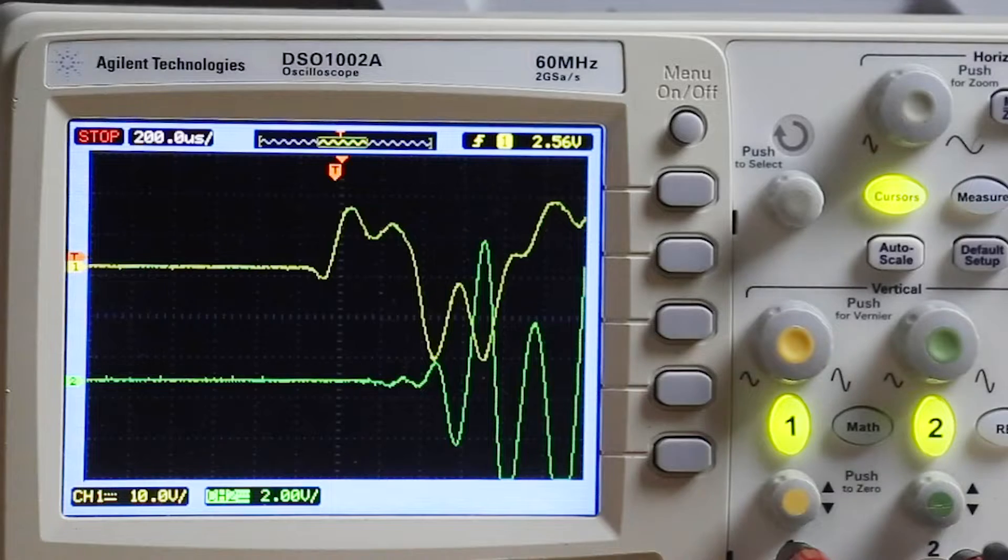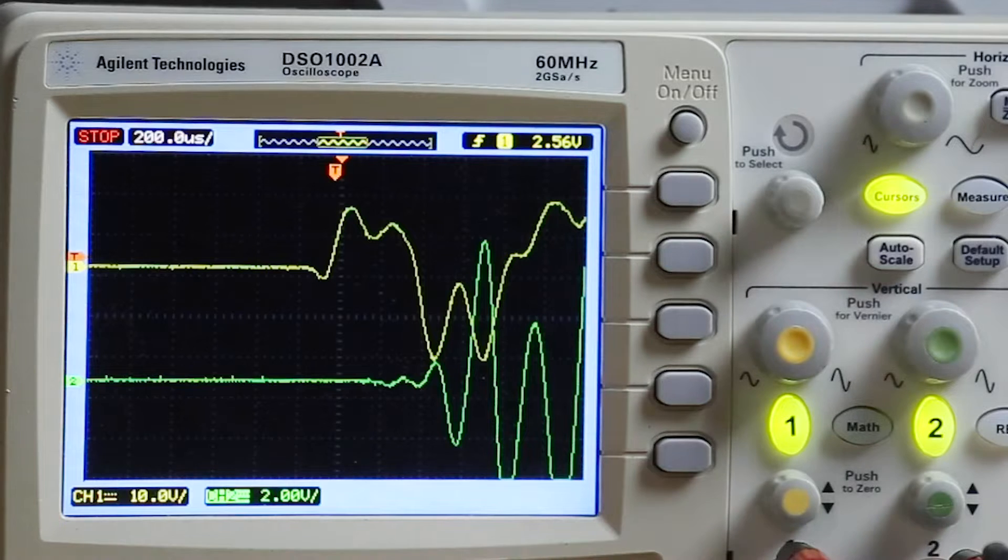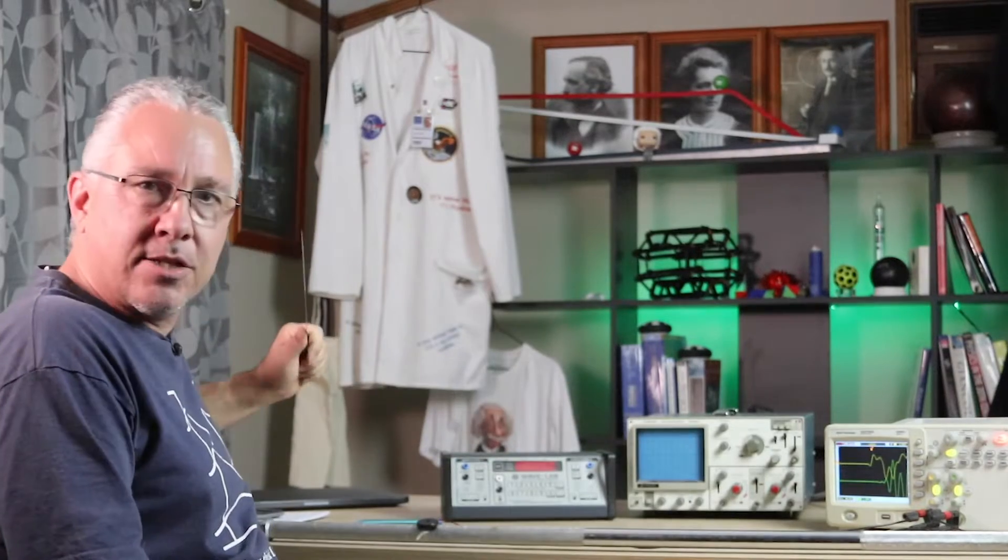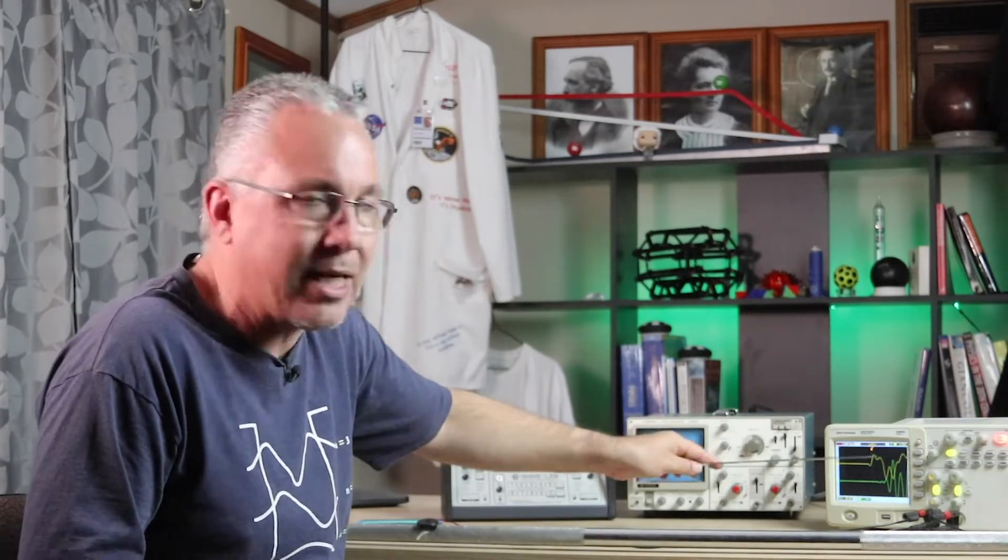The oscilloscope is going to start measuring. It will then also record the vibration of my second transducer. But because there is a delay between the start and the receiving of the signal at the other end, I should be able to work out the time delay.